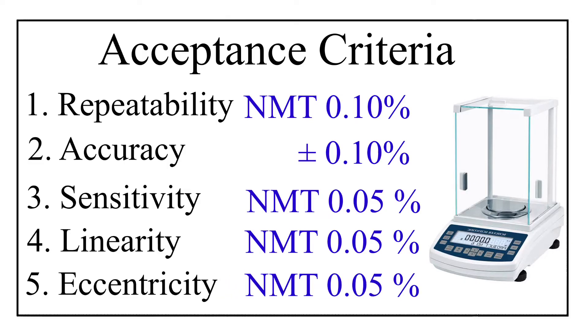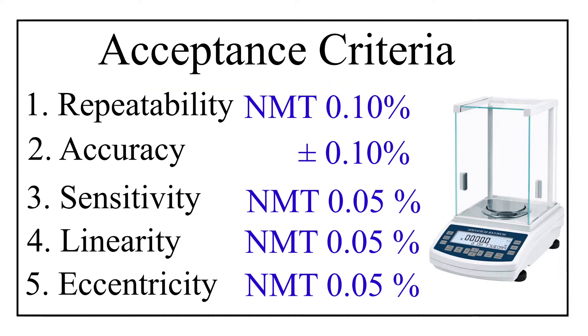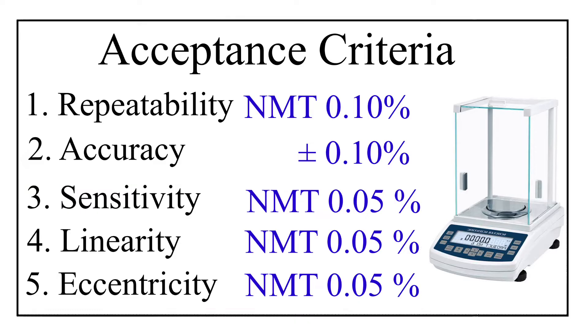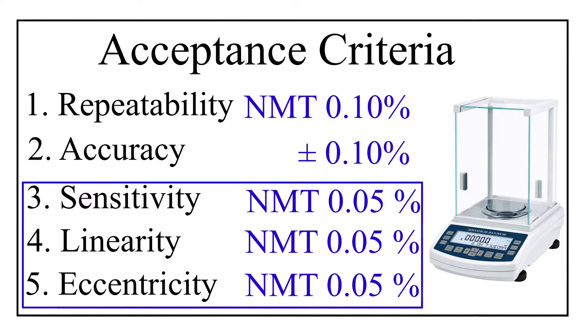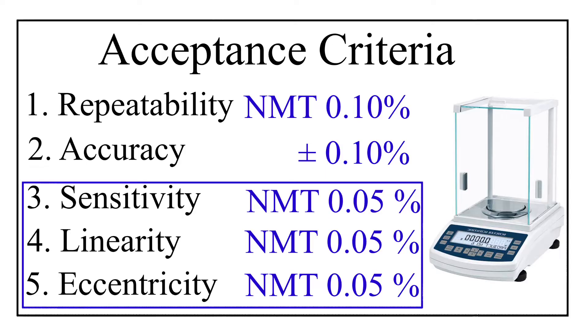To summarize, repeatability and accuracy have the same acceptance criteria, that is not more than 0.10%. And the three parameters — sensitivity, linearity, and eccentricity — share the same acceptance criteria of not more than 0.05%. That covers the acceptance criteria for all calibration parameters of a balance.